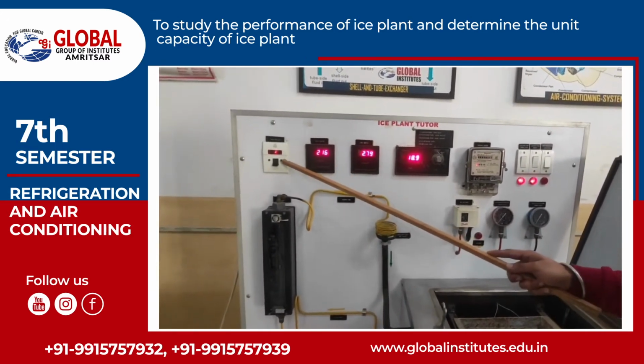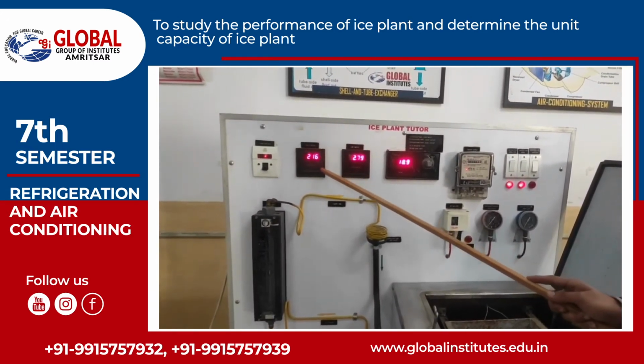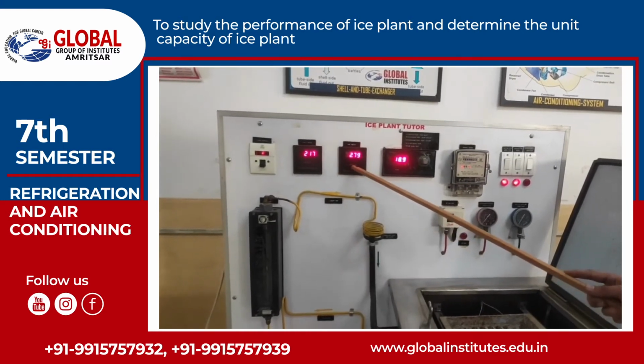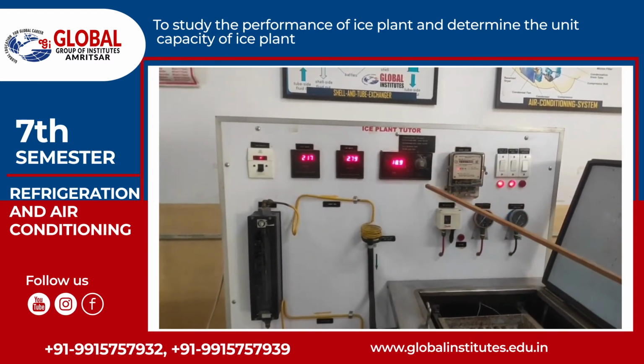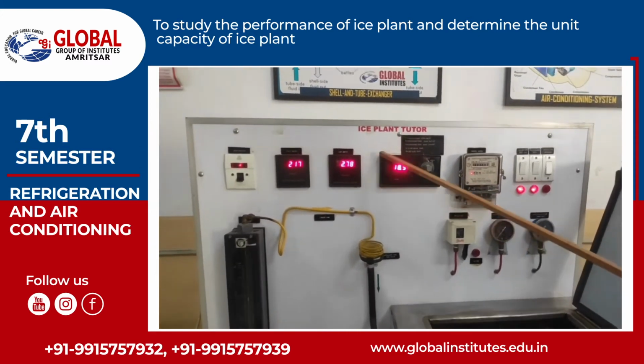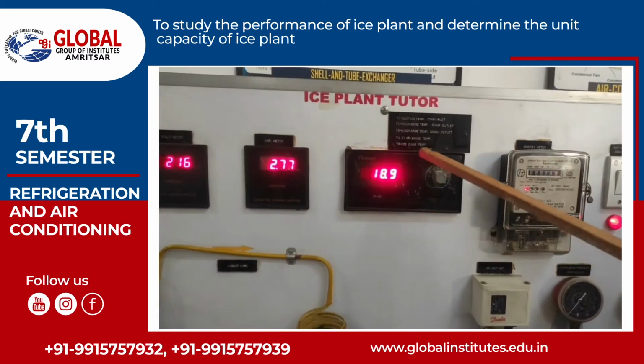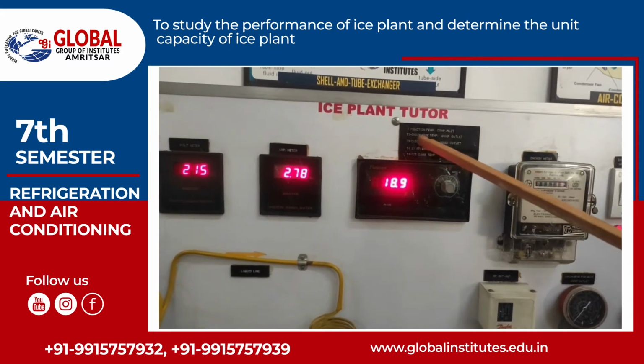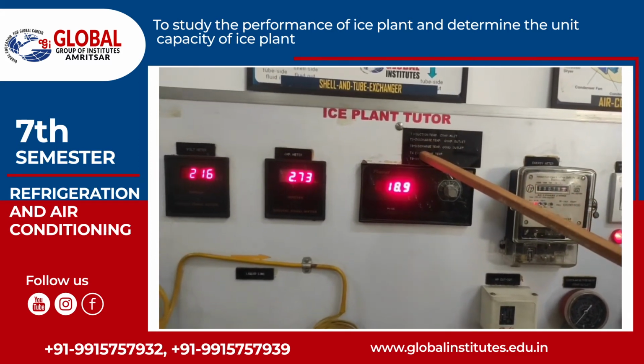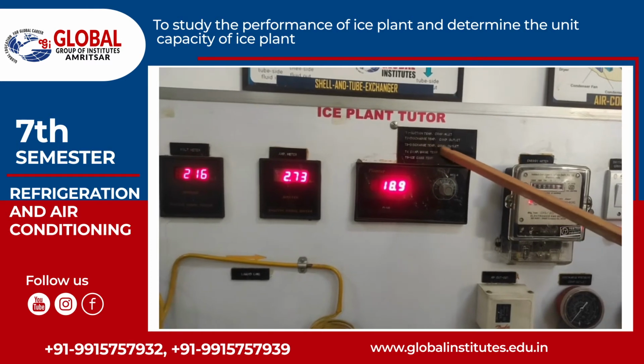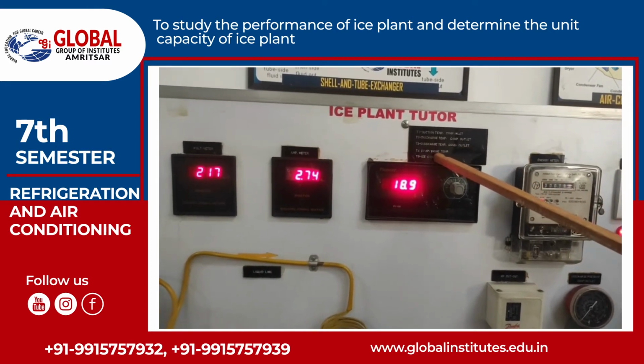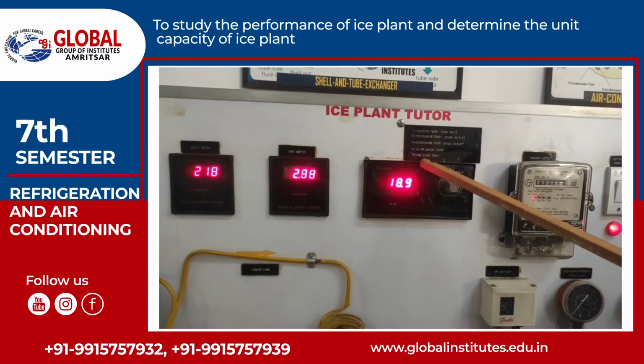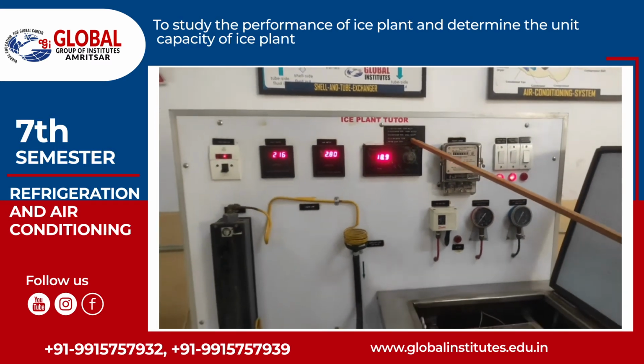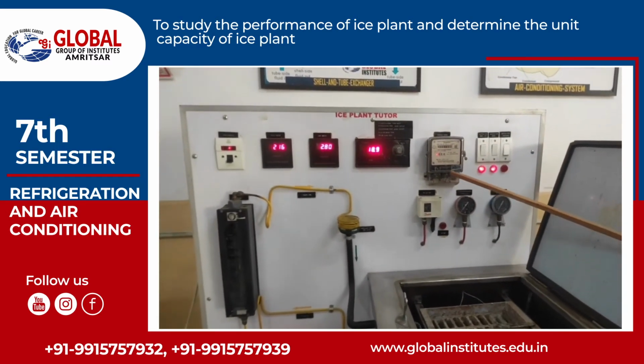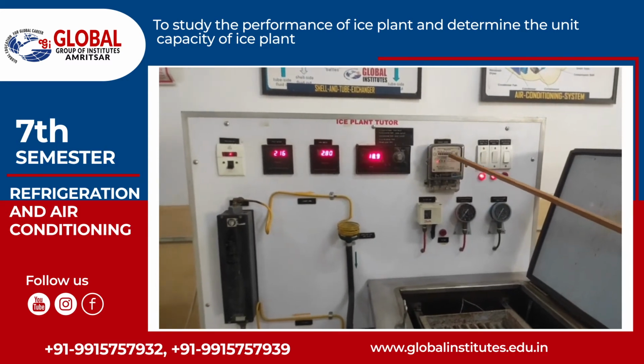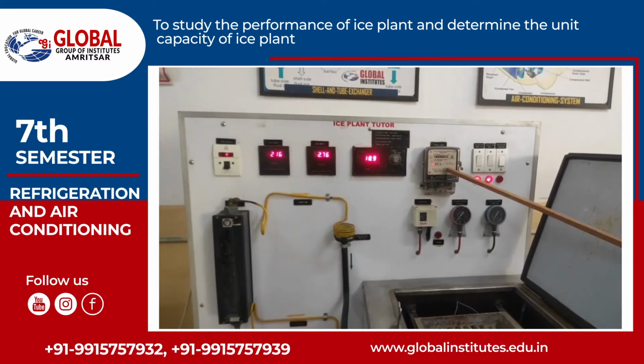The first is the main switch for the power supply, and the voltmeter and ammeter for the compressor. This is the temperature indicator to measure the various temperatures of the system. T1 is the suction temperature, T2 the discharge temperature of the compressor, T3 the discharge temperature of the condenser, T4 the evaporator or brine temperature, and T5 is the ice can temperature. This is the energy meter, used to measure the energy consumption of the compressor.